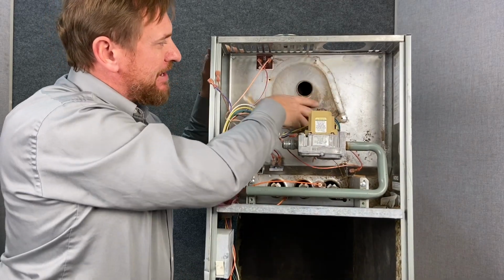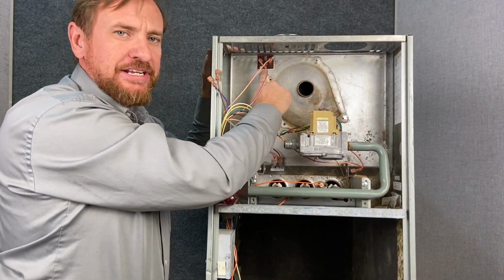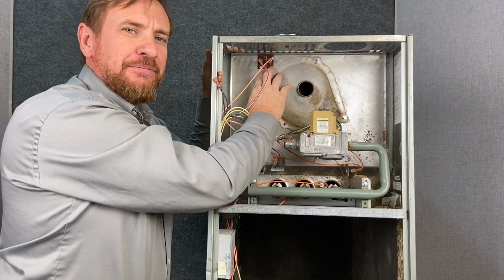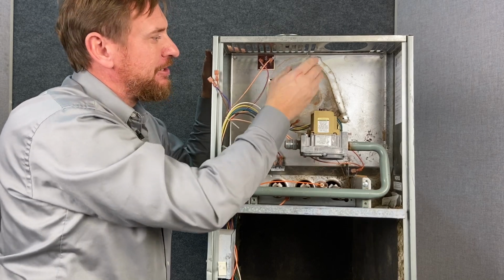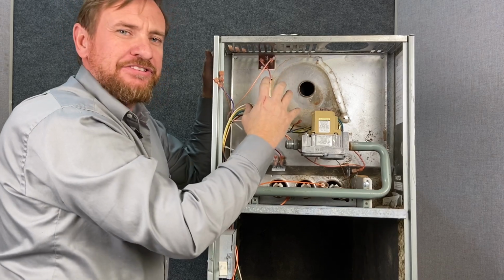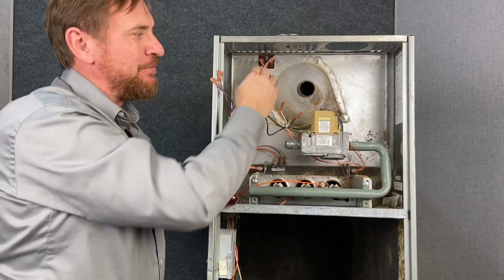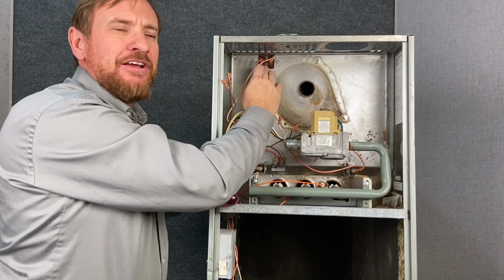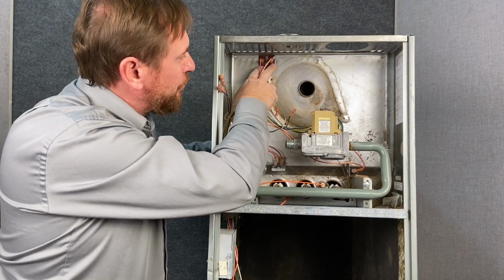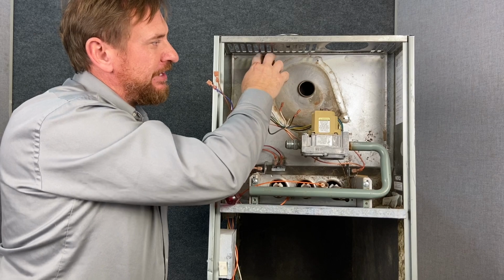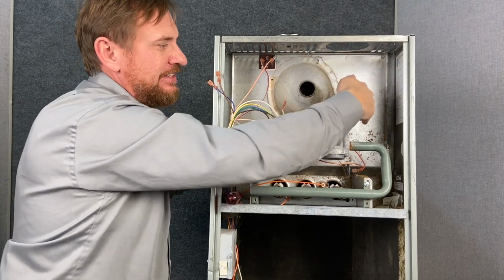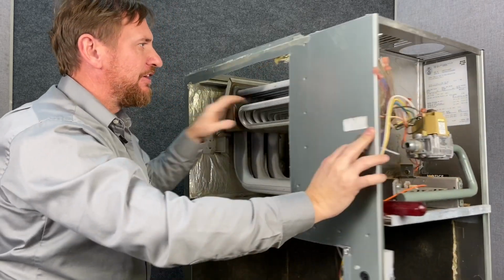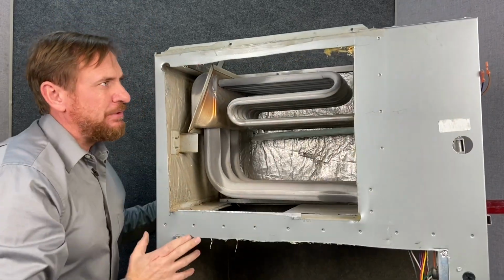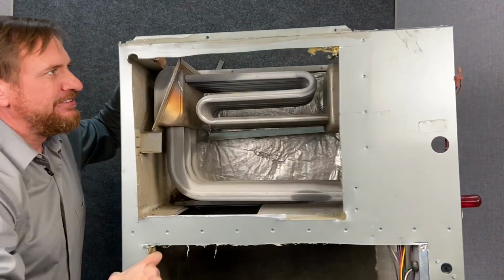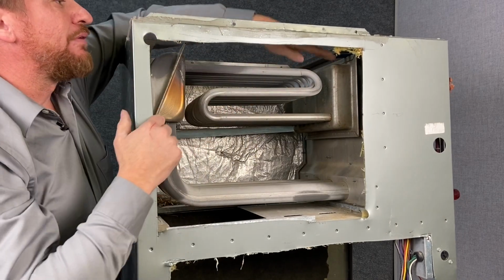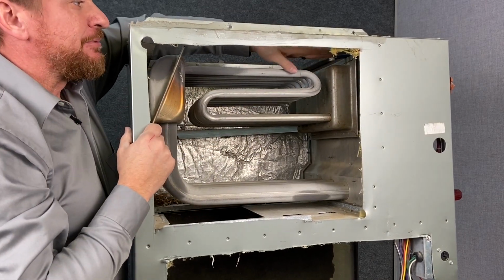So now that we have this exposed, we can see there's another component here. Now manufacturers put this component in a few different places, but it's always going to be on this panel side, but the sensor is going to be on the back side. And this is a primary limit or a high limit switch. There's going to be two wires here, usually 1 or 2 screws, and it could be here or in the center, on the sides, many different locations. But if we turn this around, we can actually see that this sensor is going to be installed right above our heat exchanger. So this is our primary limit switch.